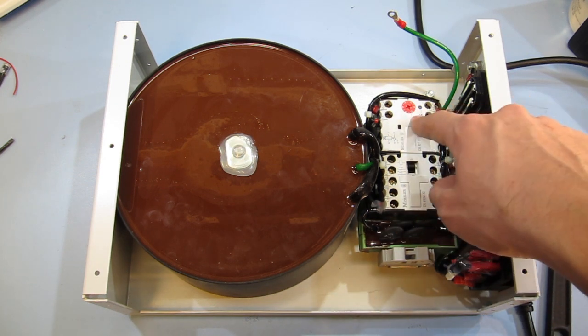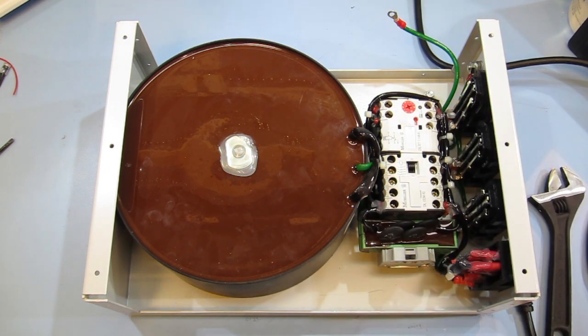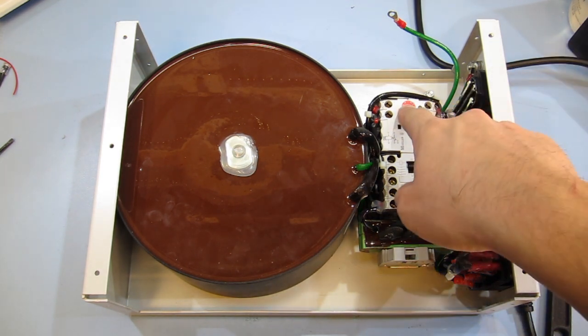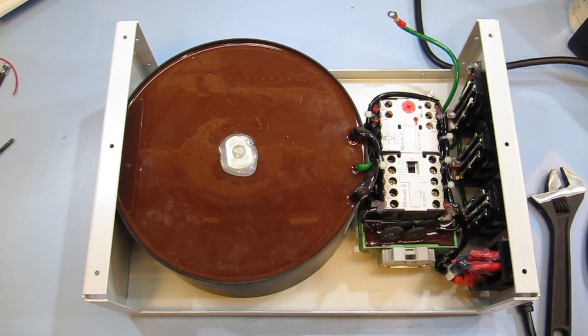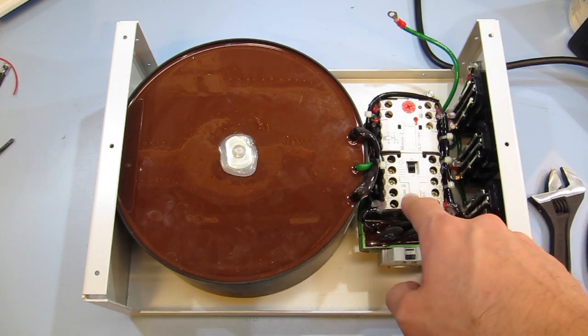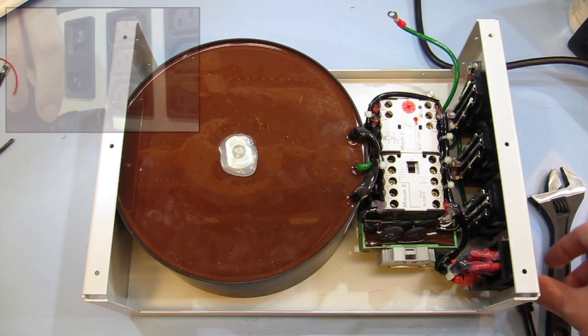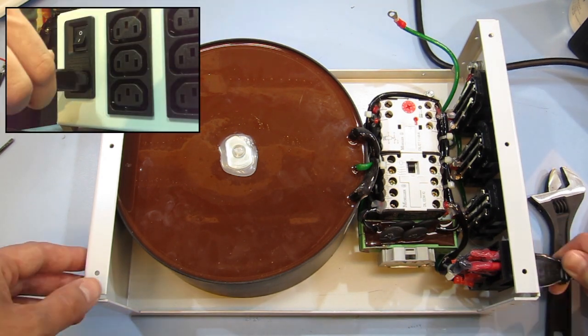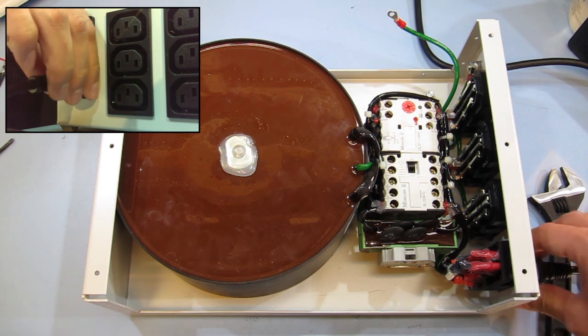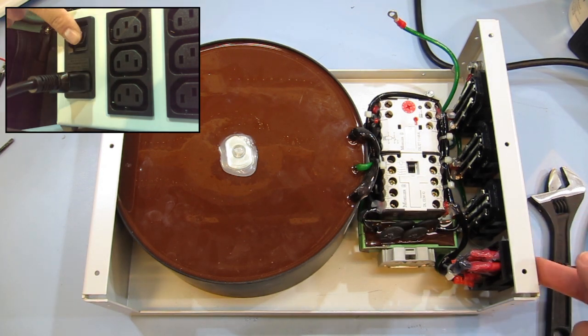It's reading 0 to 10. It's currently set to 3, and I assume that's probably hundreds of milliseconds. It's set to 3 at the moment, so it probably delays the turn on of the contactor by 300 milliseconds, but we can have a look. So if I just plug in the mains to the input jack and turn it on, so I'm turning it on now. Yeah, it's definitely less than half a second.